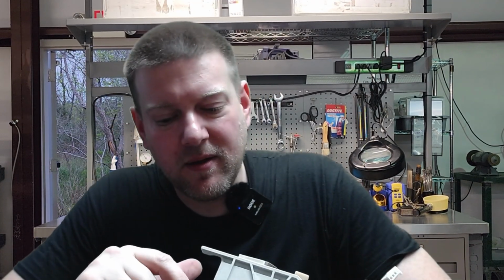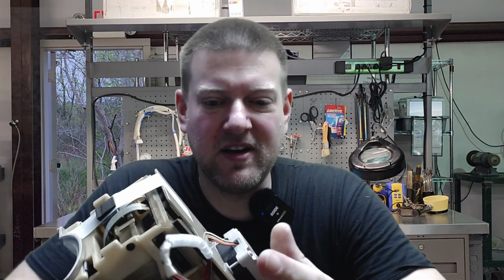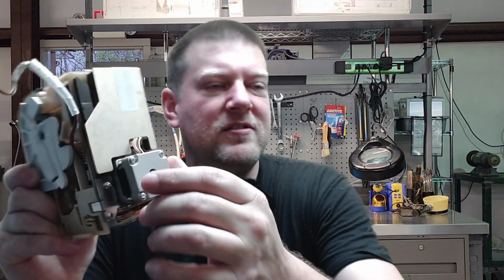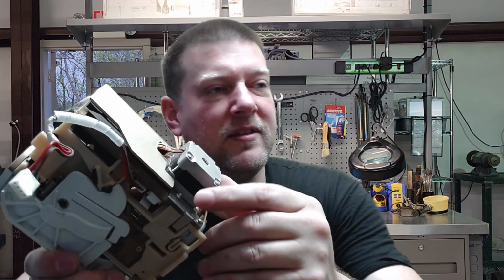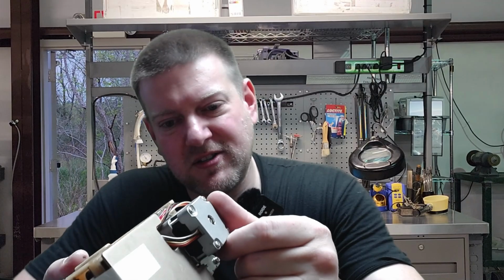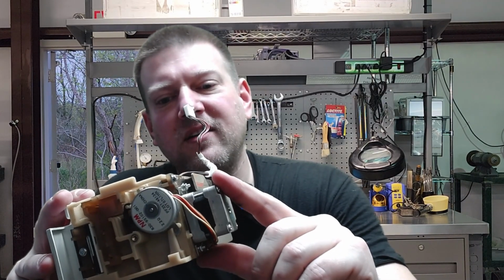And I think I can create a calibration set for these where you would put a calibration set in, load it to just under and just over occlusion pressure according to a brand new calibrated pump. And then I can get at least the occlusion calibration value. And the motor RPM, that's something that I would have to probably do very carefully. It's not going to be very easy. There are some ways of seeing the RPM on these modules. I don't know. It's going to be an interesting project I might get involved with.